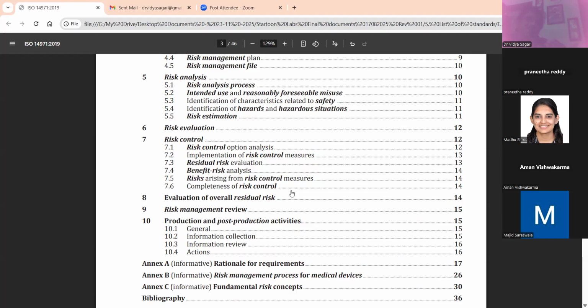Okay, this will give it, because these are coming from the clinical events. And these clinical events are coming from the residual risk, because you know what the residual risks are. So you have usability engineering coming in here. And you have the risk management which is sitting in the center. And you have your clinical evaluation reports. And from all these three, you derive the IFU. Okay. All of them are interconnected.